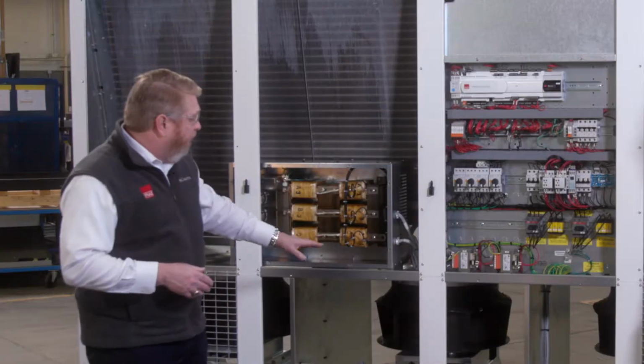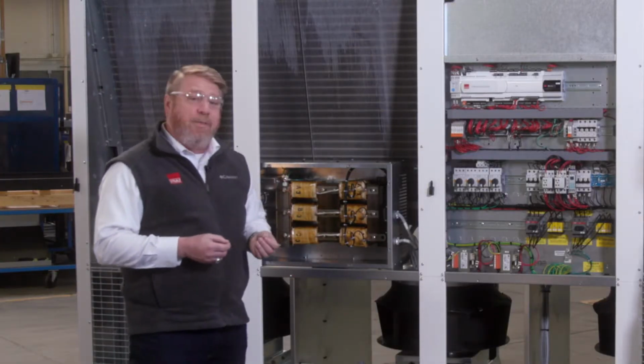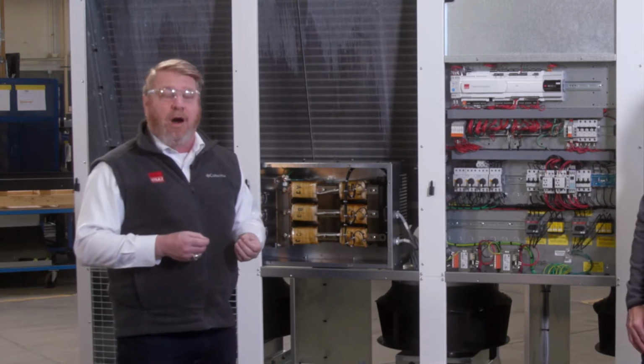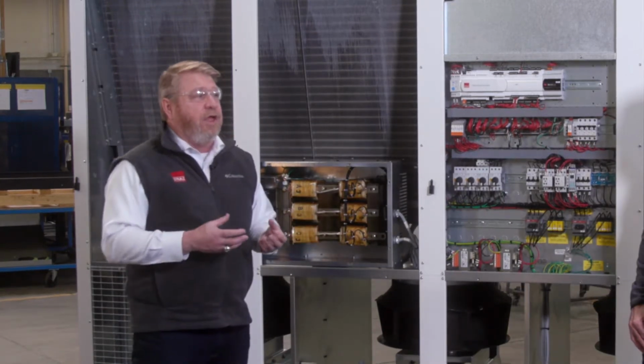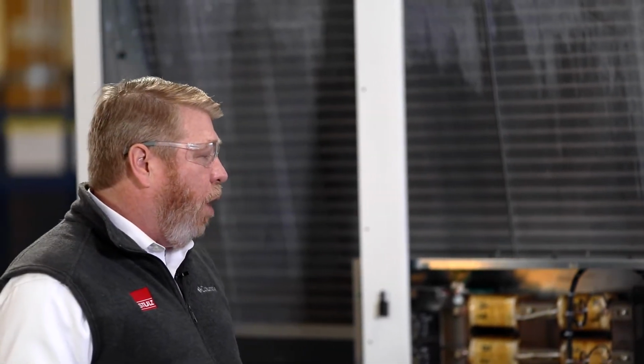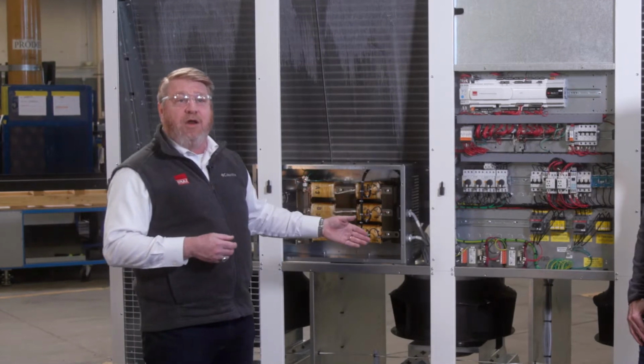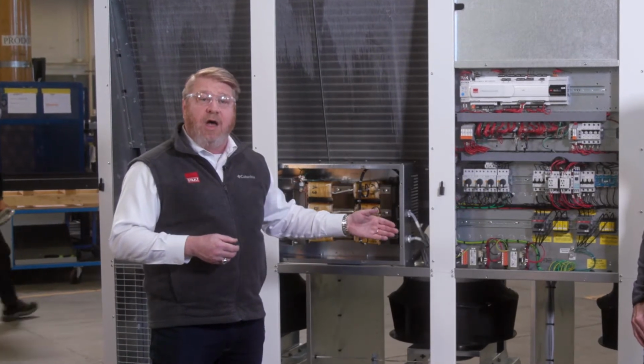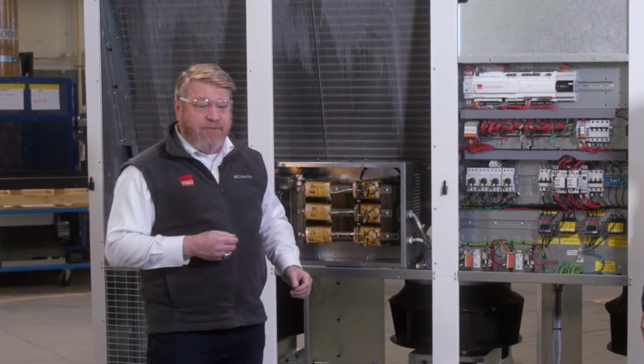Now, these were introduced relatively recently, and the real advantage of the composite fan blade is unlike the older style aluminum fan blade, the fan blades can be made in a shape that makes them highly efficient for moving air. A lot of that has to do with the actual airfoil shape of the impeller blades that you can now do with the composite material that you could not do before. The composite material does meet all the smoke and flame requirements of UL 1995.